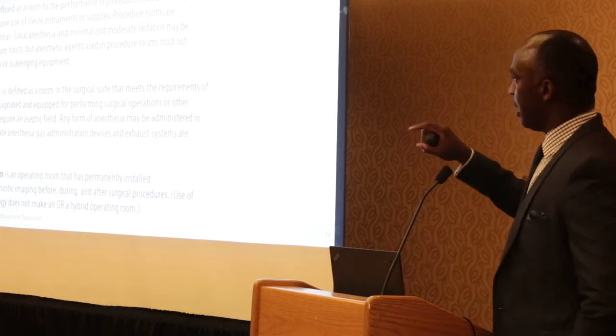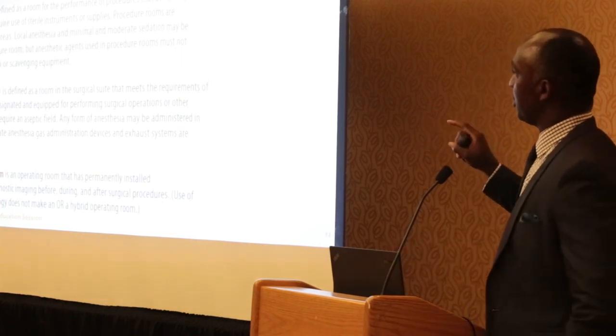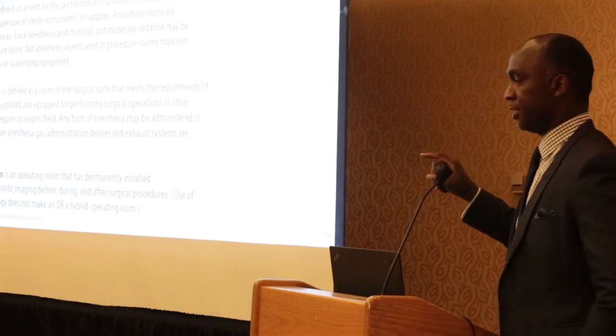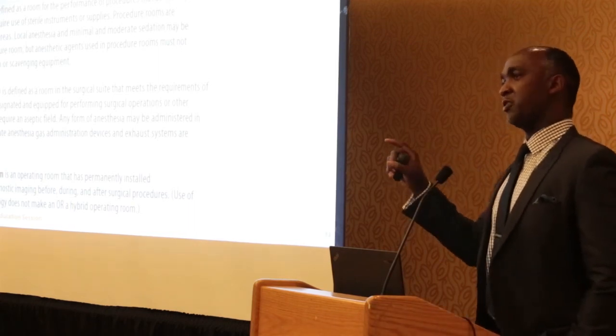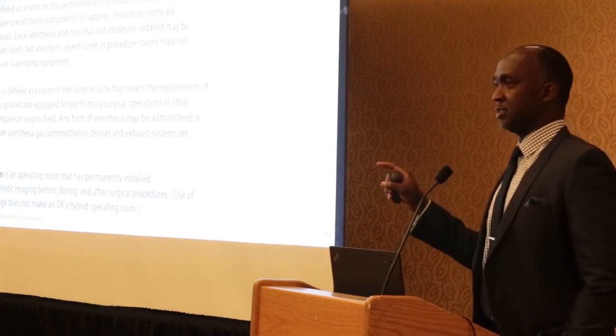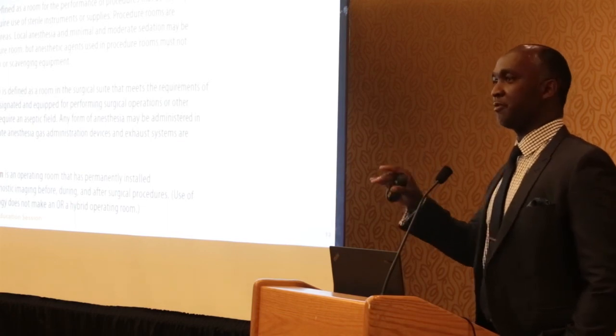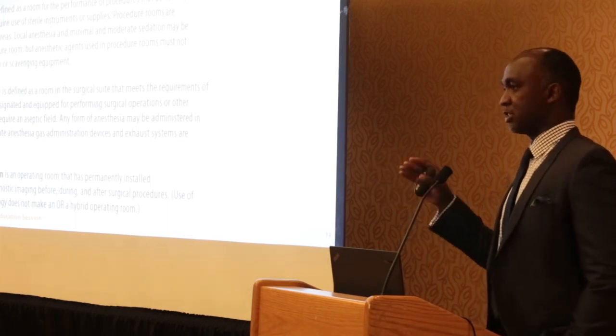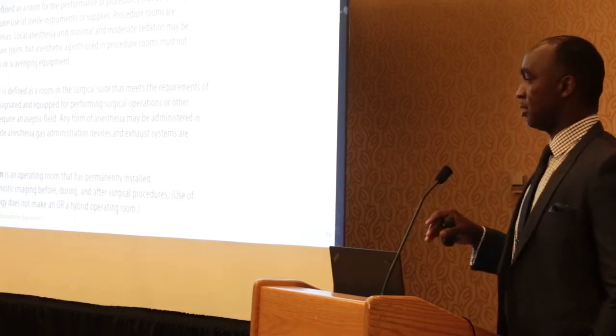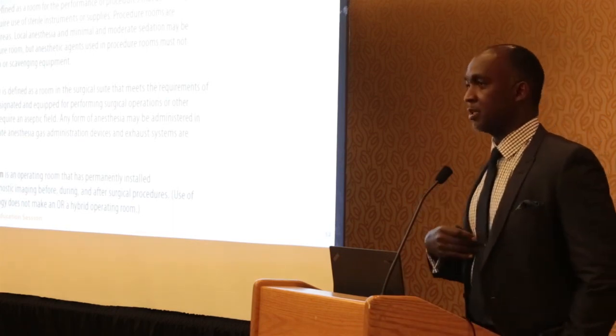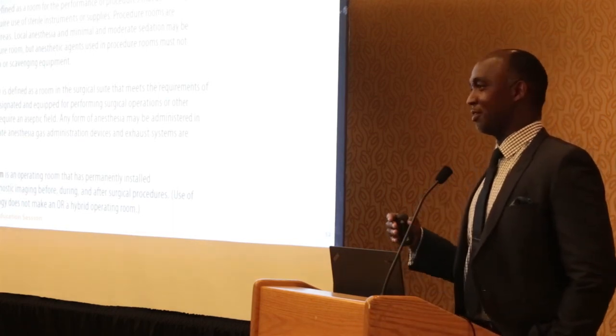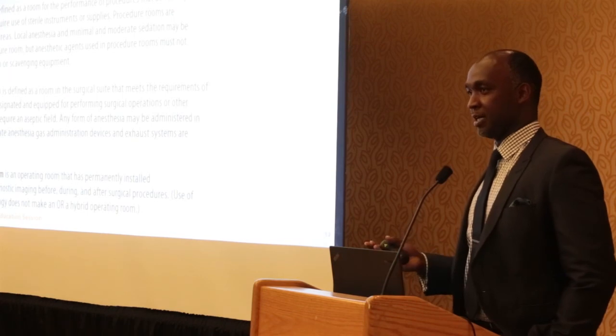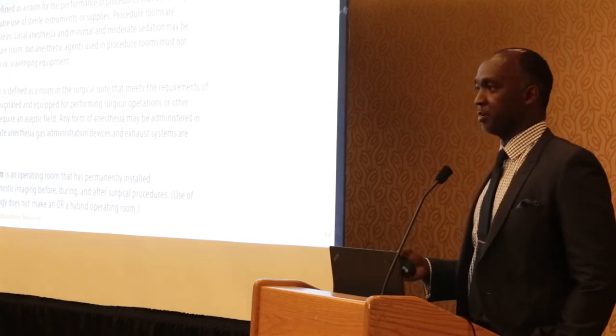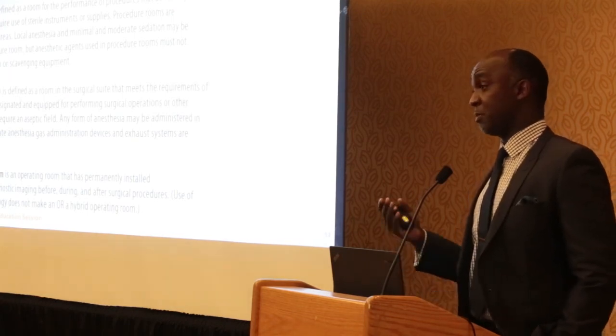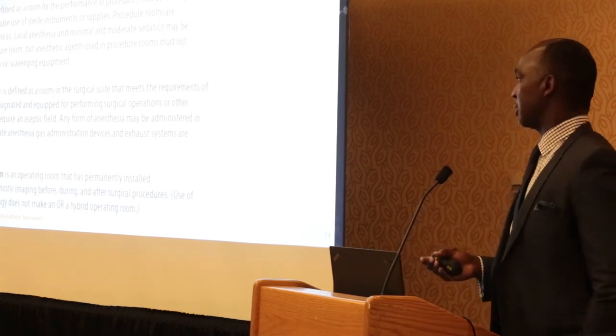Procedure rooms just talk about restricted or unrestricted areas, and you don't have to have local anesthesia; if you have it, you don't have to have an exhaust system. That's what a procedure room is. In my design, most operating rooms are procedure rooms—that's how you design it. They have the same air change rate and almost the same conditions, maybe a little smaller, but basically the same.